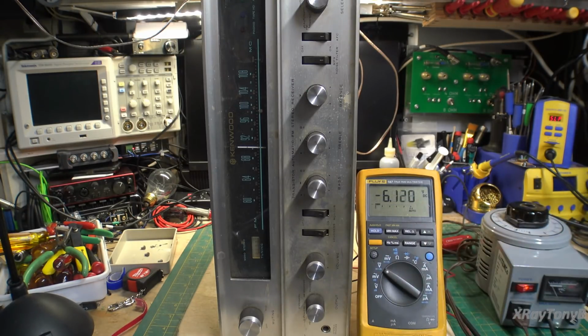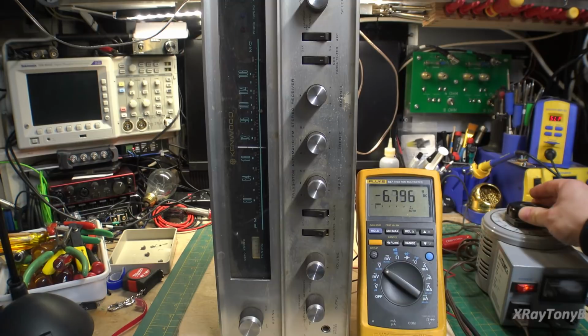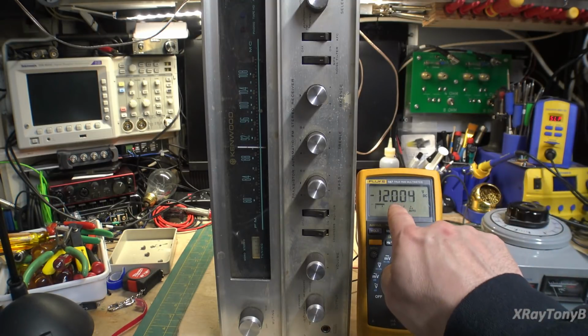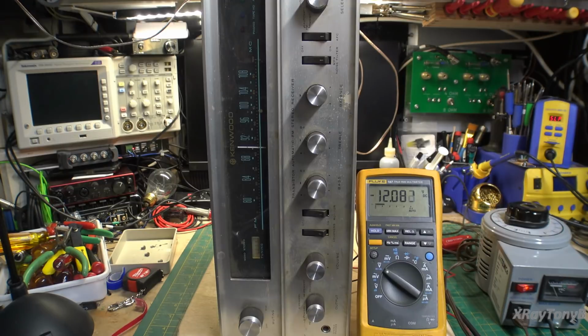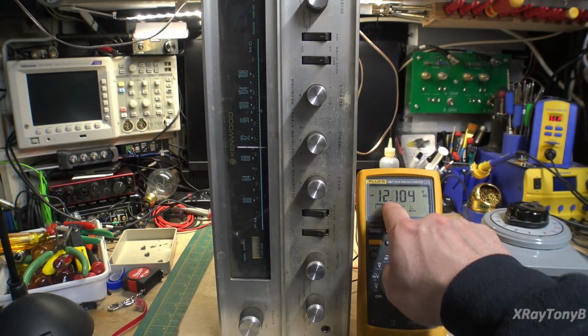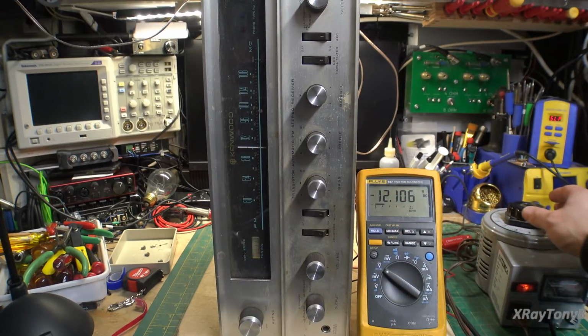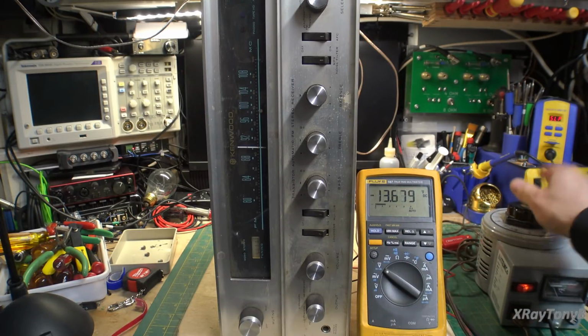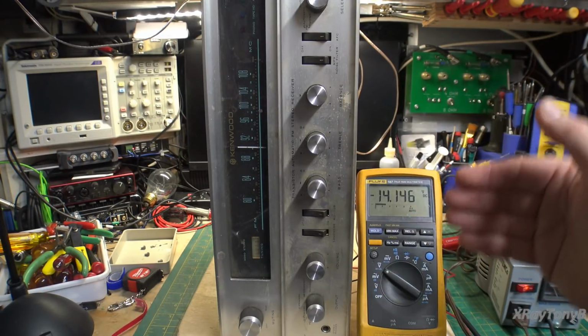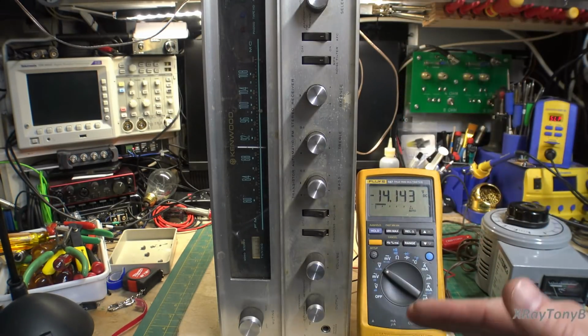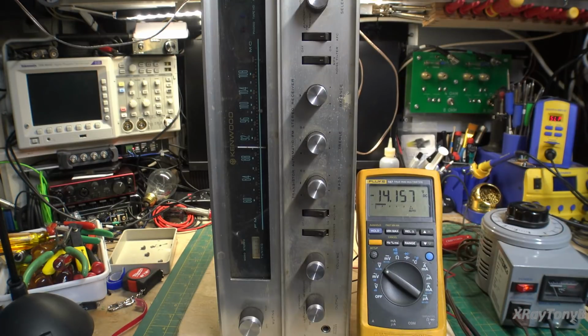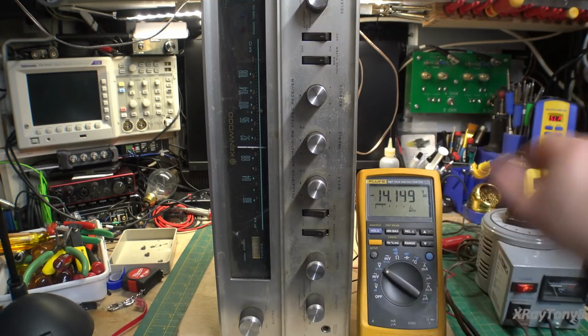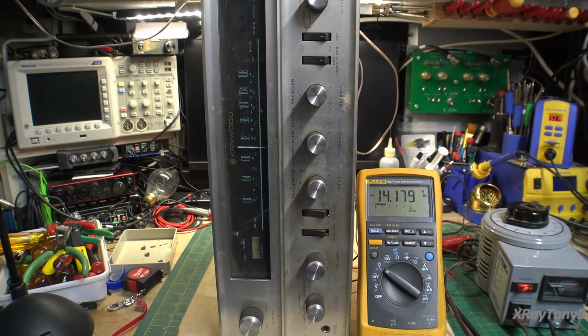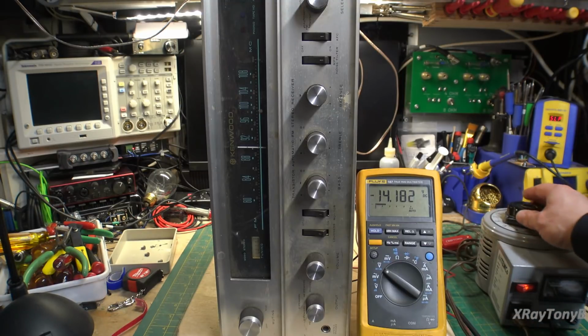And you can see already it's starting to charge the capacitors on the power supply. And the idea is you just want to watch this. A telltale sign, if you're drawing heavy current, is the voltage will climb like this. It'll climb gradually. But you'll get to a point where if something starts to short out or draw heavy current, you'll see this voltage rapidly drop. It'll just suddenly drop. When you see that, when you're using the variac method, there's something that's not right. You turn it off very quickly, and you have to find what your problem is.